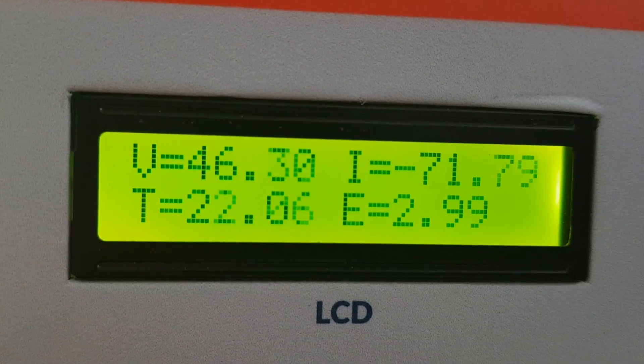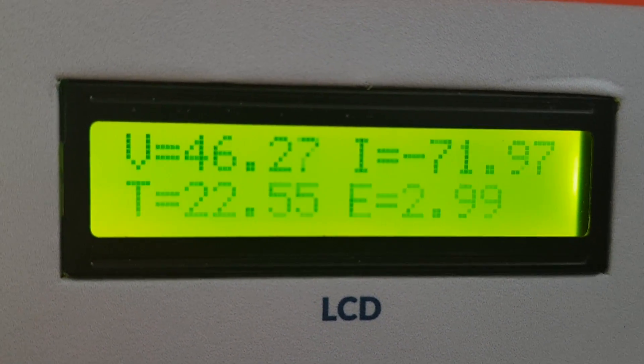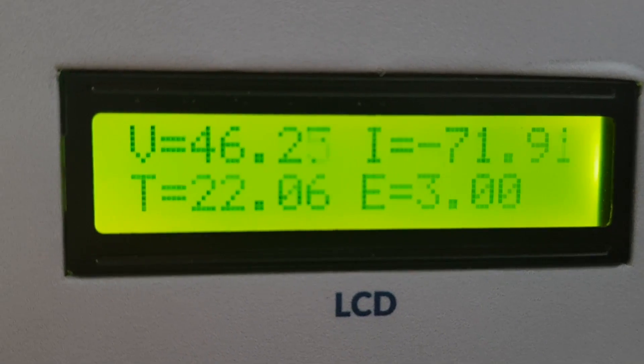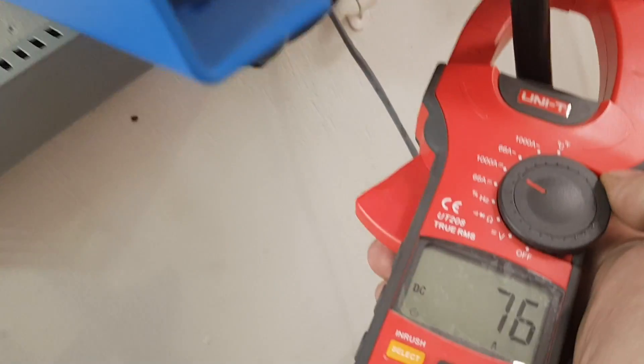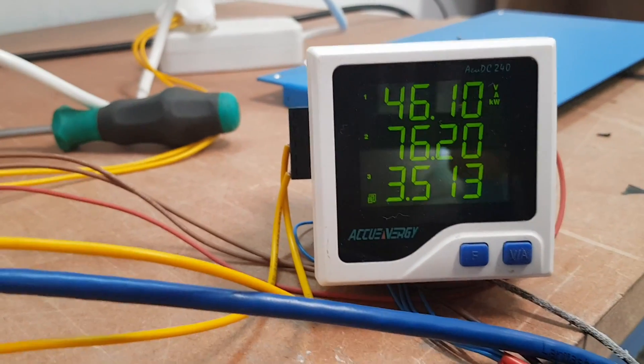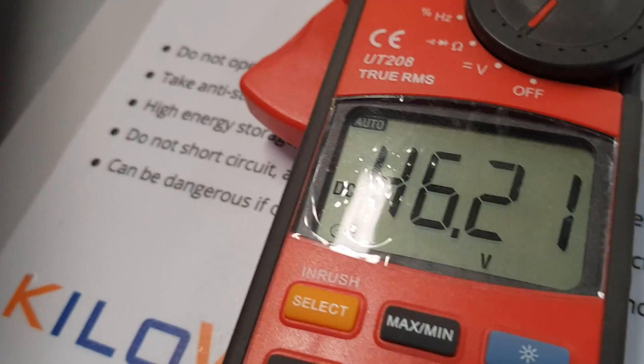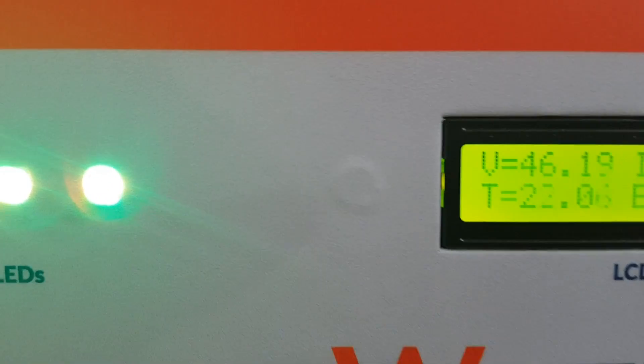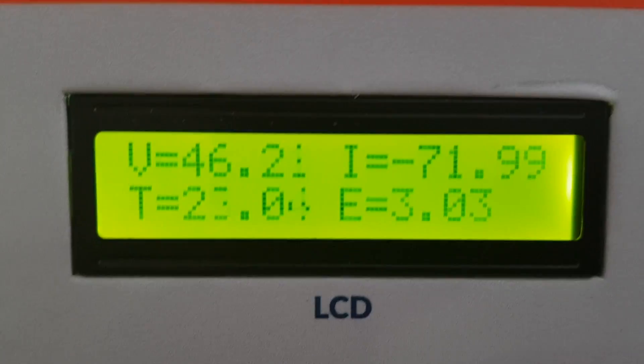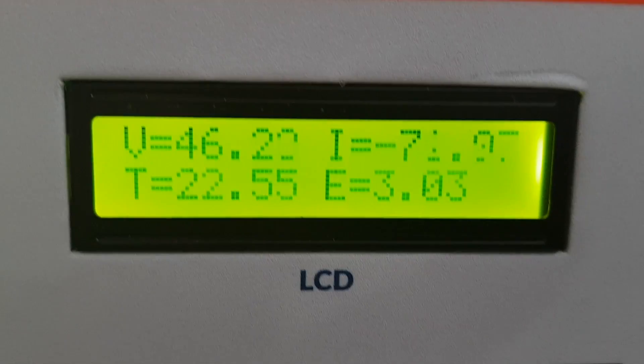There's definitely a big concern regarding the energy calculation, also the voltage and current measurements — seeing 46.27V and 71.8 amps internally. If we then go over to the calibrated ammeter, the current is actually 76 amps, only 72 on the internal meter. Here's the calibrated meter showing the same 76 amps and 46.1 volts at the terminals of the battery. Measuring 46.2 volts on the terminal as well, but the current showing significantly less — and the energy calculation is the one that concerns me.